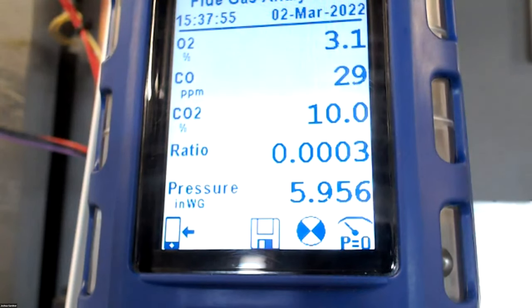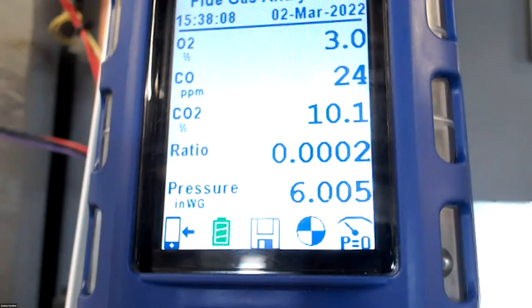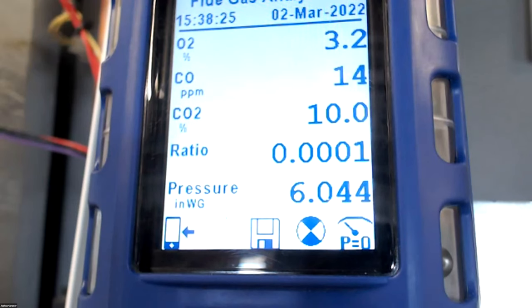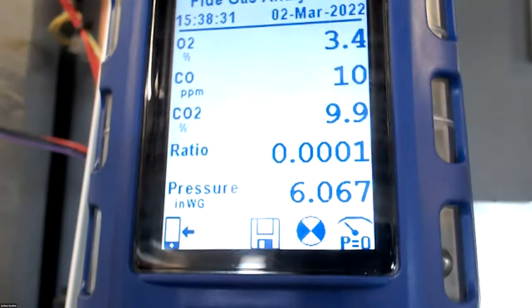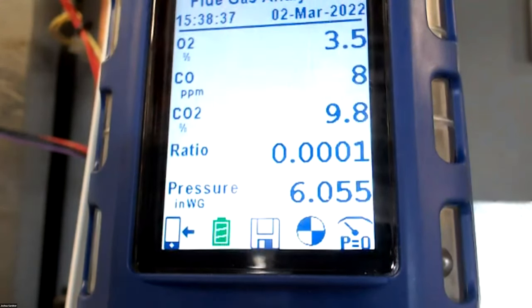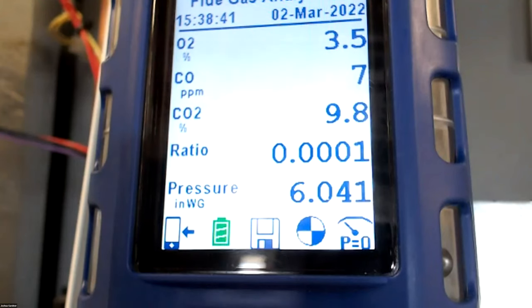So in our manual, we have some parameters to be between. My CO2 wants to be between 9 and 10.5, and my target is 9.5. My O2 should be between 2.15 and 4.85 with a target of 3.95. And then my max CO needs to be below 150 parts per million on high fire and below 10 parts per million on low fire. So right now I'm at low fire, and it looks pretty good. I'm within my specs.